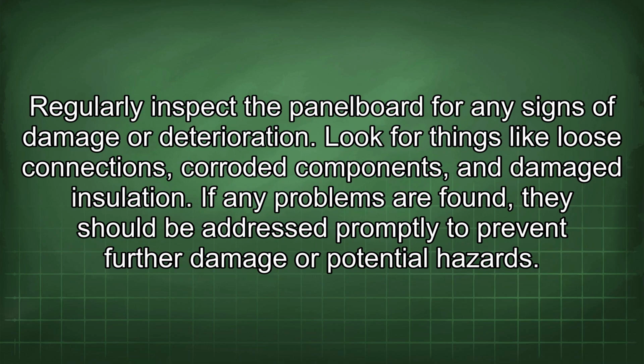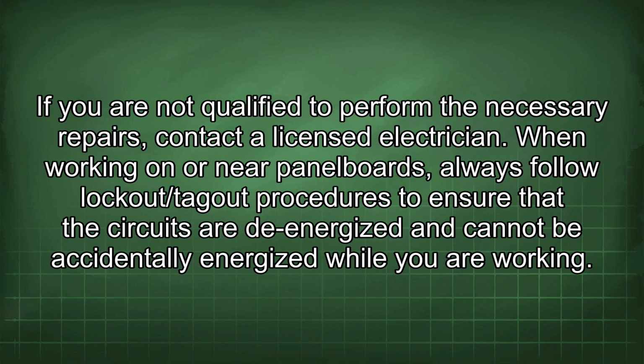Regularly inspect the panel board for any signs of damage or deterioration. Look for things like loose connections, corroded components, and damaged insulation. If any problems are found, they should be addressed promptly to prevent further damage or potential hazards. If you are not qualified to perform the necessary repairs, contact a licensed electrician.